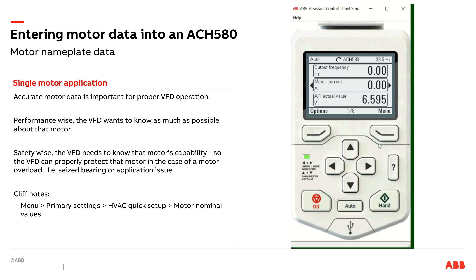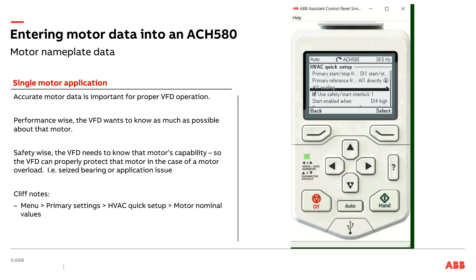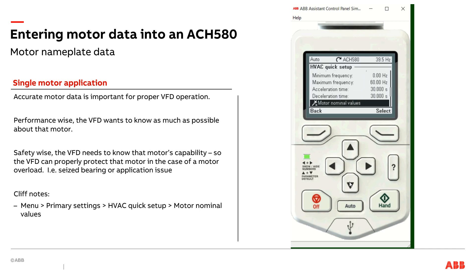I'm going to click on Menu, go to Primary Settings. I like to do a lot of my work whenever possible within the HVAC Quick Setup. So I'm going to go into the HVAC Quick Setup — a lot of my typical startup data is going to go into this area of the drive, and the motor data is a great example. So I'm going to scroll down here to Motor Nominal Values.